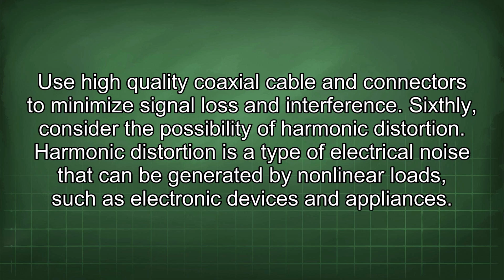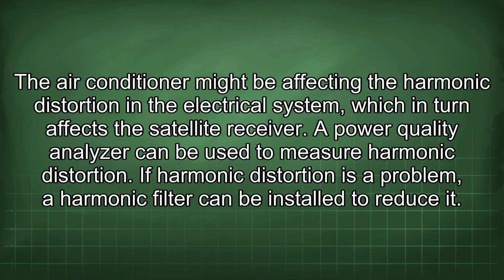Sixthly, consider the possibility of harmonic distortion. Harmonic distortion is a type of electrical noise that can be generated by nonlinear loads, such as electronic devices and appliances. The air conditioner might be affecting the harmonic distortion in the electrical system, which in turn affects the satellite receiver. A power quality analyzer can be used to measure harmonic distortion. If harmonic distortion is a problem, a harmonic filter can be installed to reduce it.